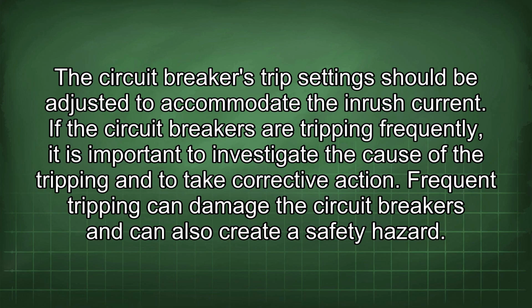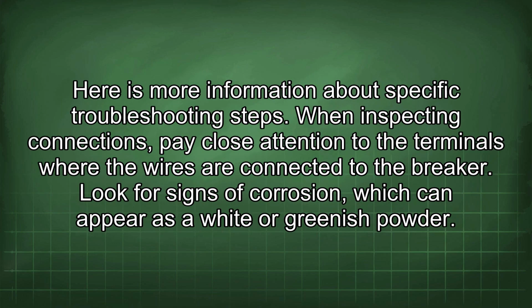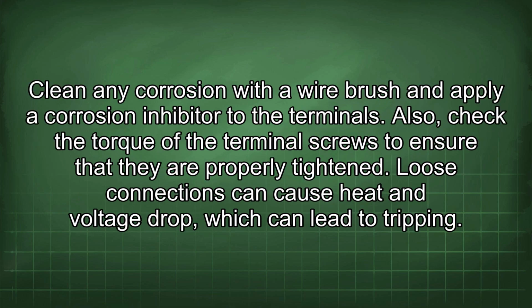If the circuit breakers are tripping frequently, it is important to investigate the cause of the tripping and to take corrective action. Frequent tripping can damage the circuit breakers and can also create a safety hazard. Here is more information about specific troubleshooting steps. When inspecting connections, pay close attention to the terminals where the wires are connected to the breaker. Look for signs of corrosion, which can appear as a white or greenish powder. Clean any corrosion with a wire brush and apply a corrosion inhibitor to the terminals. Also, check the torque of the terminal screws to ensure that they are properly tightened. Loose connections can cause heat and voltage drop, which can lead to tripping.